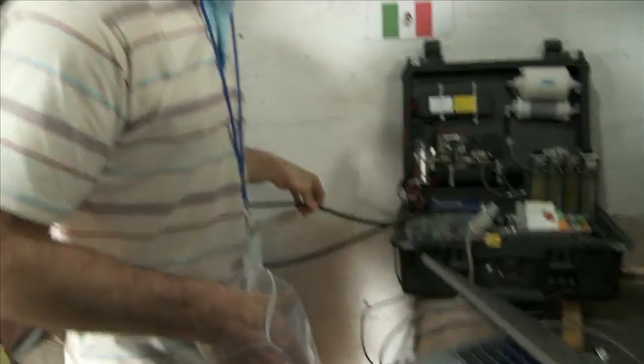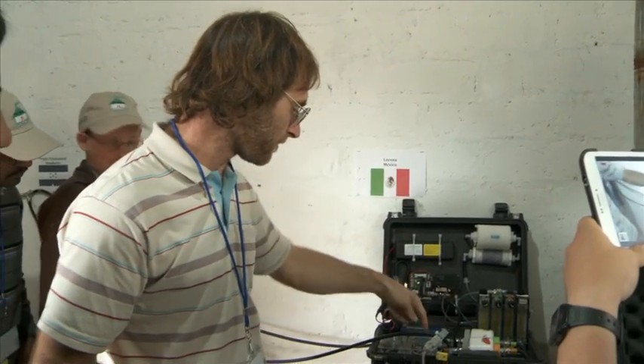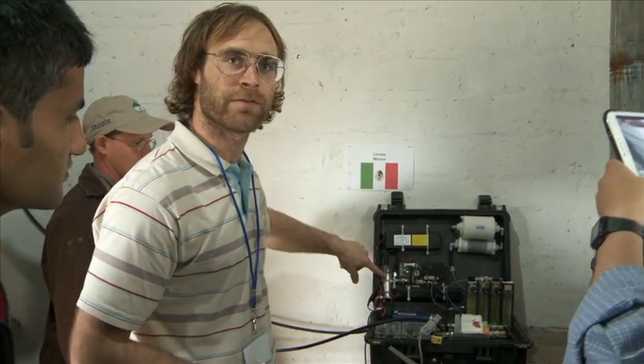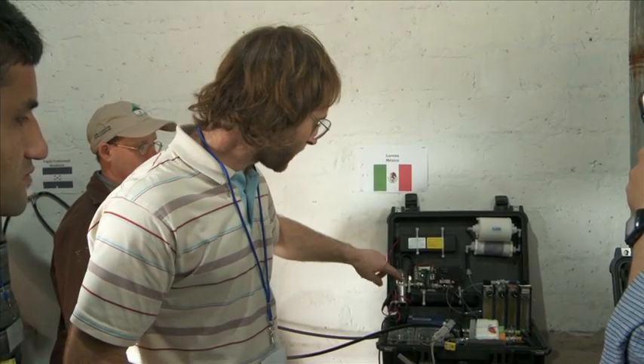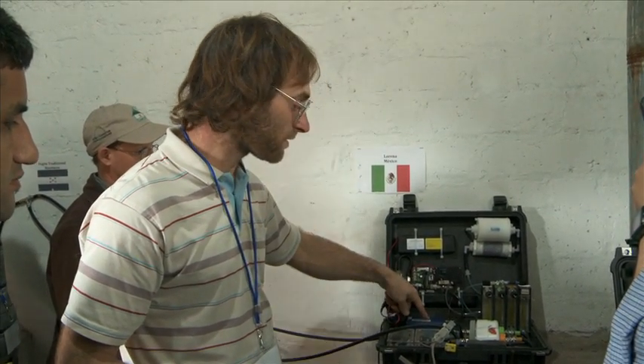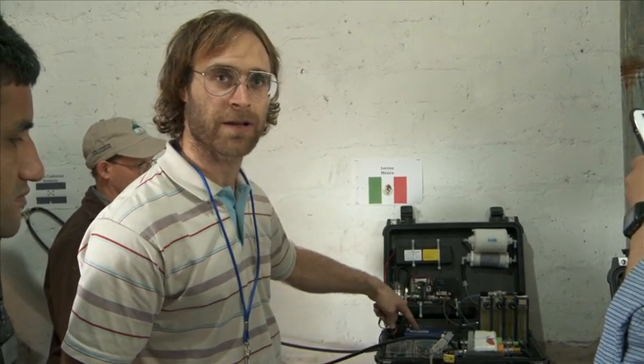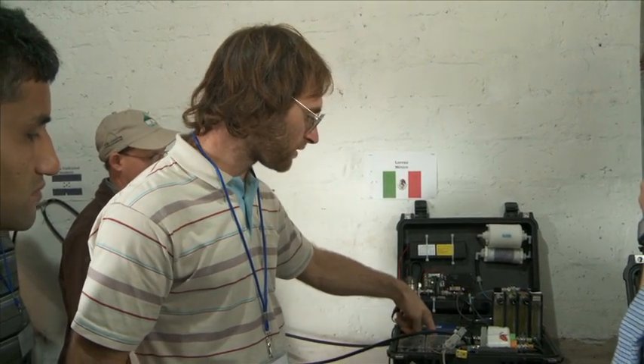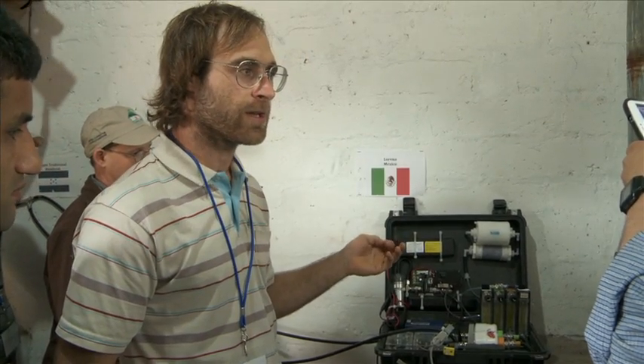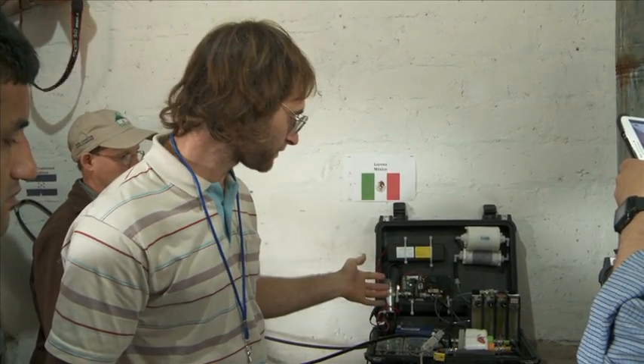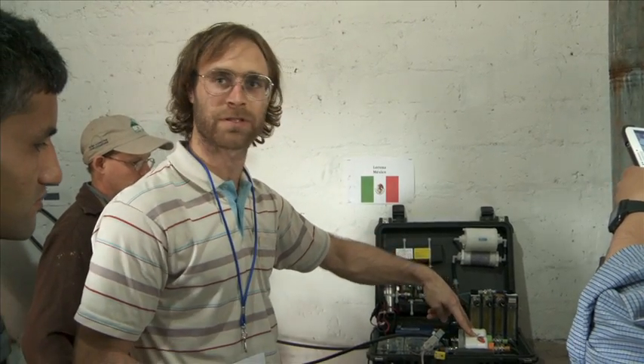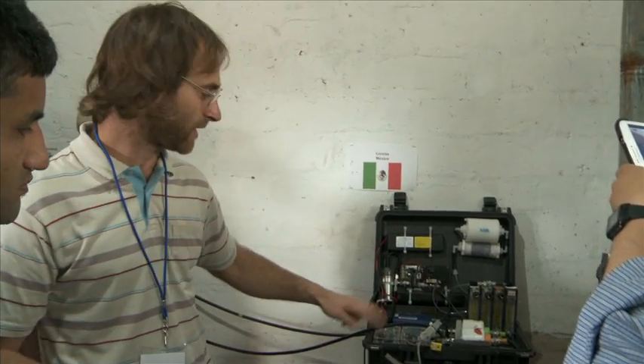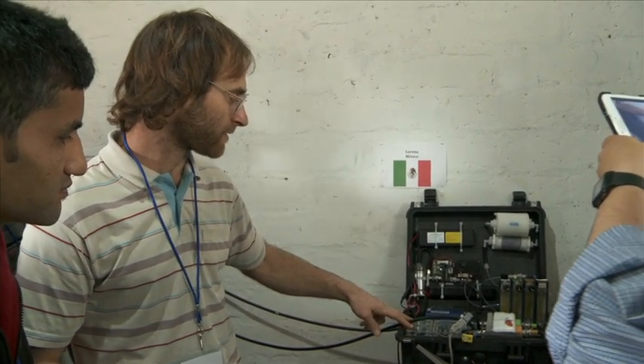Can you explain what this equipment is? Yeah, so the sample comes in here from the probe. It's drawn in from a pump underneath the panel, and it comes through the cyclone, which takes out the larger particles. A part of the sample goes through the microaethalometer to measure the black carbon. The rest of the sample goes down underneath the panel where it's measured by the optical particulate matter sensors. And then it comes up and goes through these filters. So we collect the smoke on the filters to weigh them. And then it goes through the gas sensors to measure the carbon monoxide and carbon dioxide concentration.